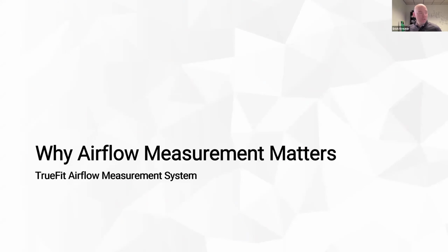So to get right into it, why do we measure airflow, specifically outdoor airflow? And what are the common issues that we see with technologies that, as an industry, we use what we can and we put it where we have to, and a lot of times that leads to not necessarily the most ideal situation and measurements.